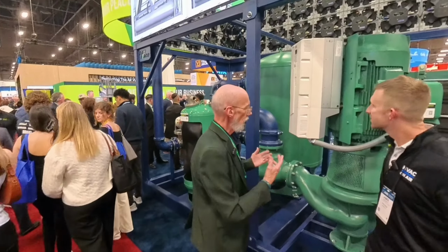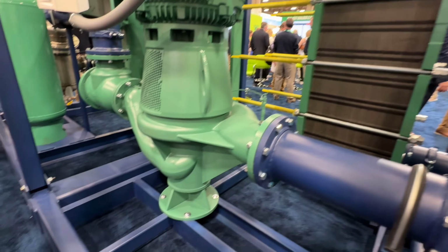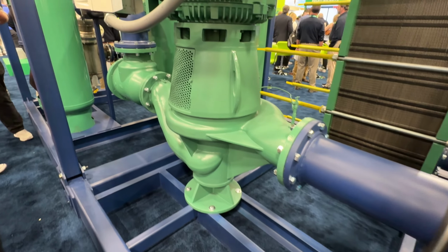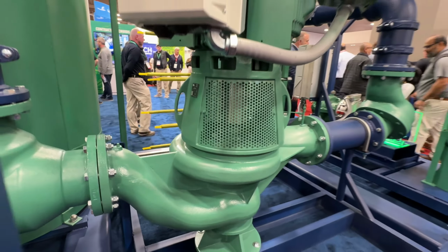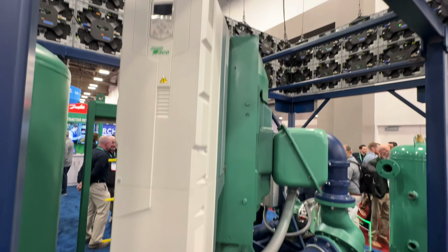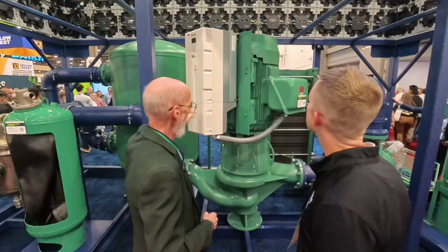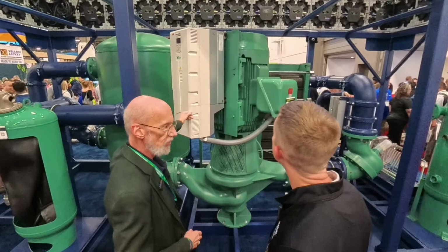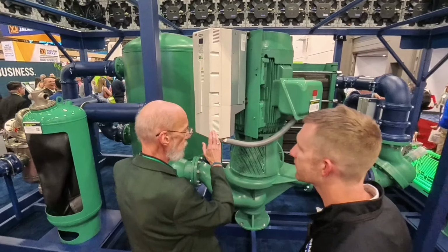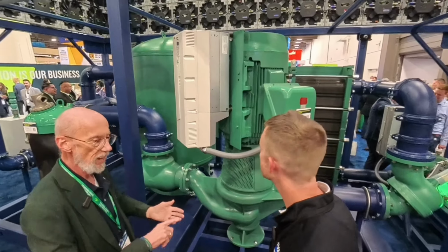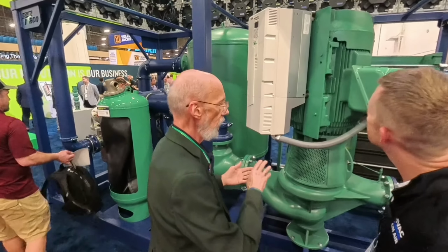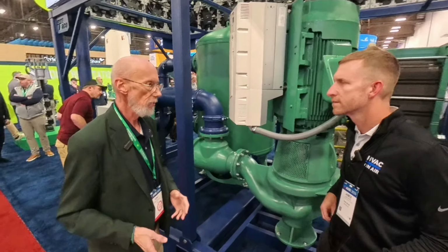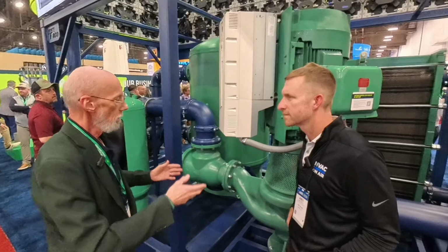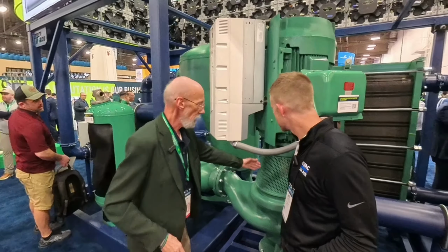So, we've built vertical inline pumps for a long time. We've done unit mounted drives for a very long time. This is a 125 horsepower vertical inline pump. We have the capabilities of doing self-sensing with this drive. From the factory, it comes pre-programmed, pre-set up, ready to go, eliminates the risk from having to program the drives in the field. The other advantage is this is a split coupled design.